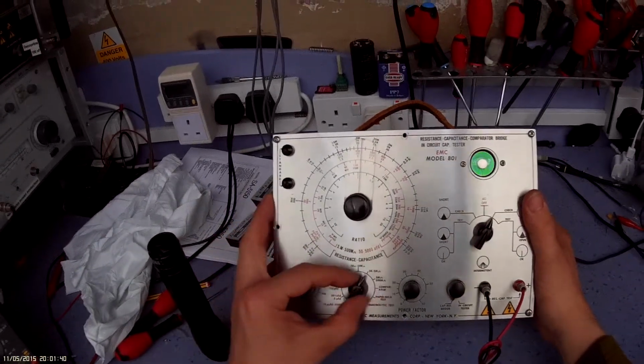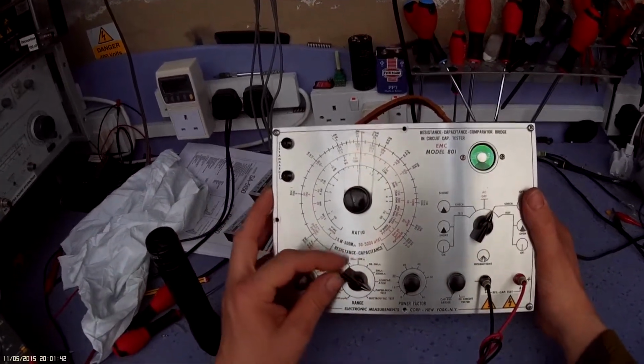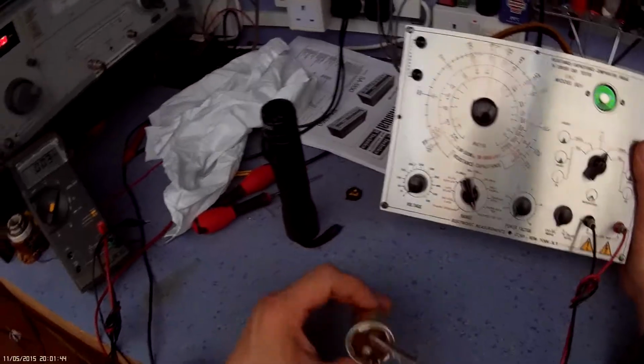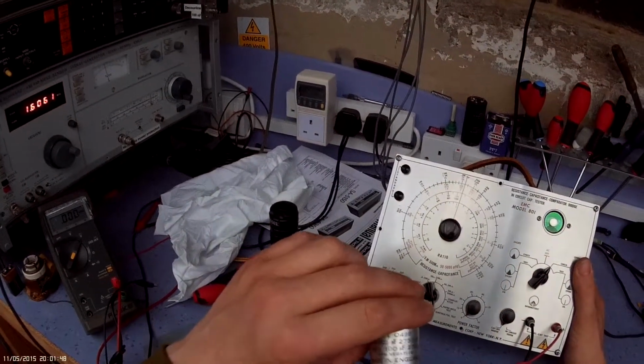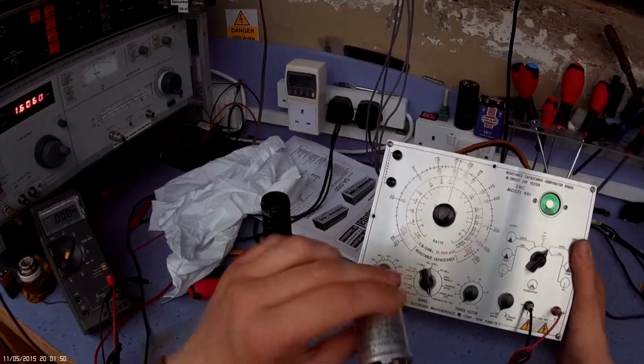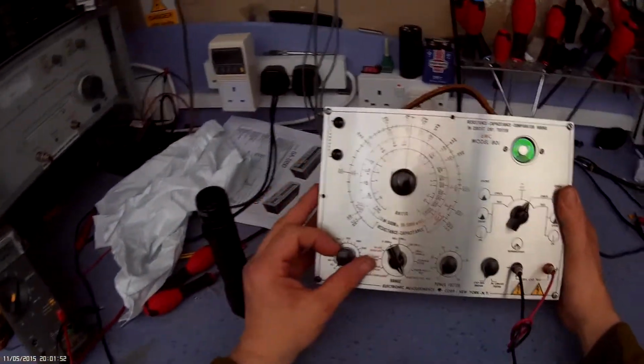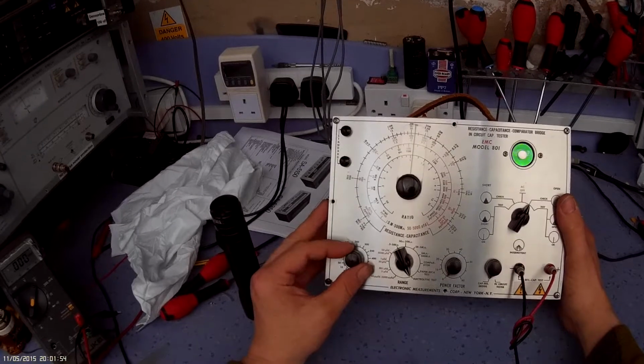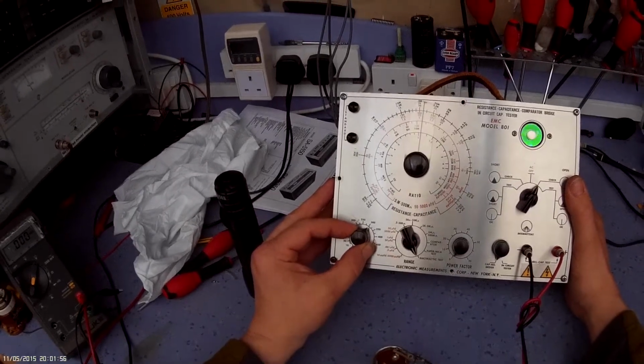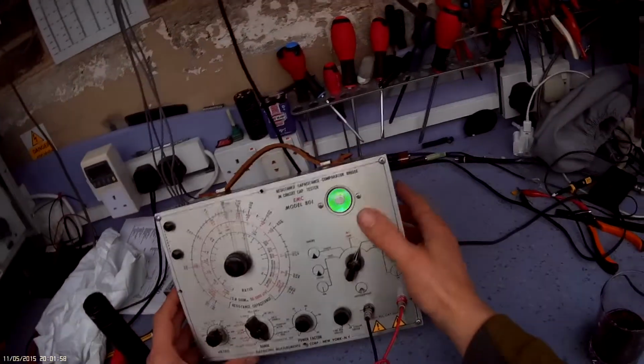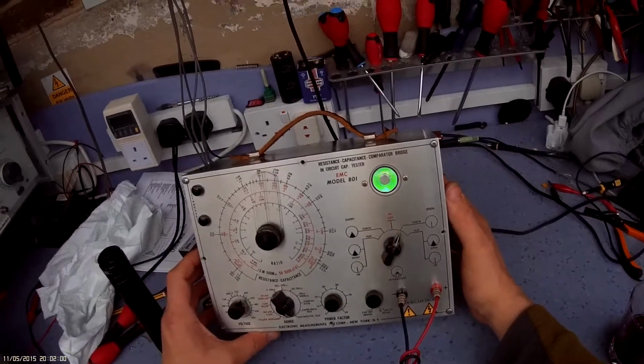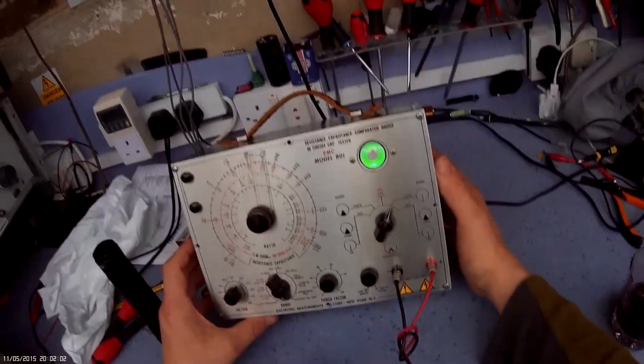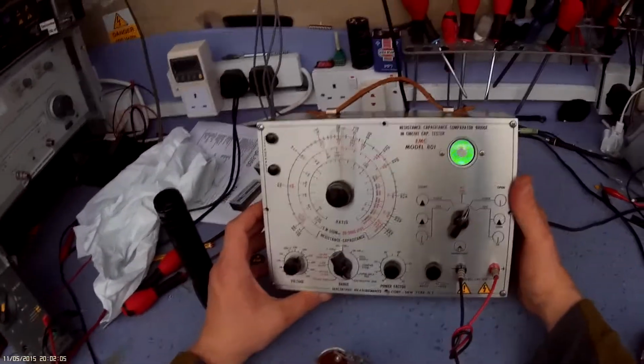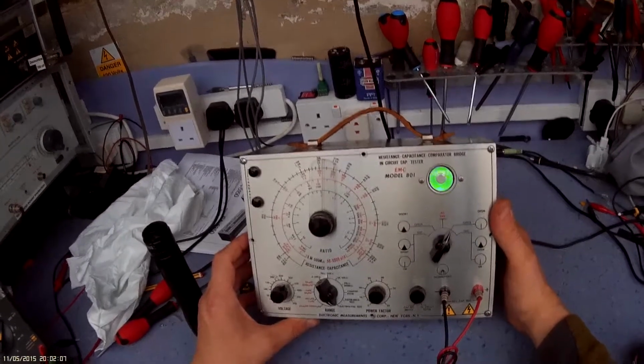But the power factor doesn't drop back that much, so that looks okay. The other test it will do is a voltage test, so you can test the capacitor at its rated voltage, and this is where you have to be a bit careful. This cap's rated at 275 volts on the yellow scale, so you can apply a voltage up to 275 volts and just wait for the eye to open. It should open at 275 volts. If it doesn't open, it means the capacitor's leaky and shouldn't be used at its rated voltage.